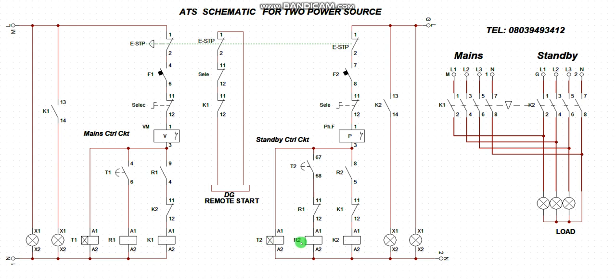A timer must not energize a contactor, because this timer sometimes must be fragile due to some electronic components. Some timers that are integrated with components are very sensitive to inductive load. And this contactor coil is an inductive load. So a timer is not expected to feed an inductive load directly. It should feed a relay. So it's feeding this relay, and this particular relay now feeds my contactor, okay? So the contactor closes, I'll now have power here.